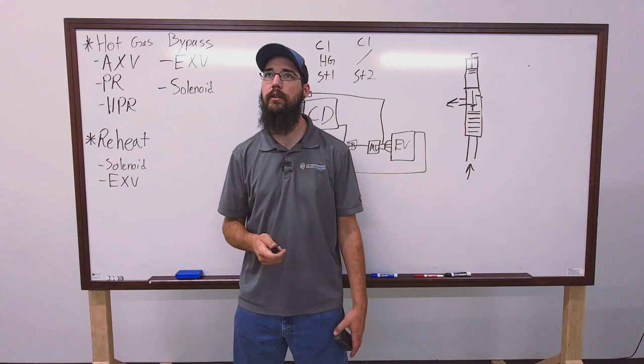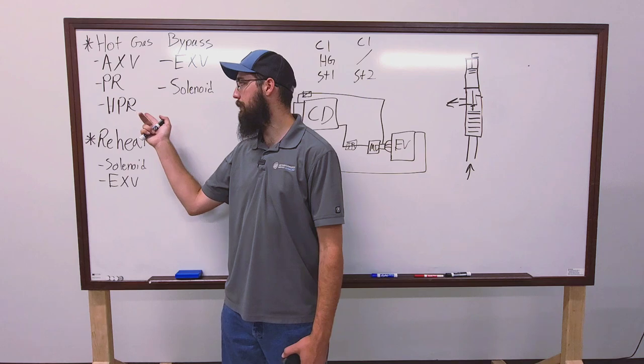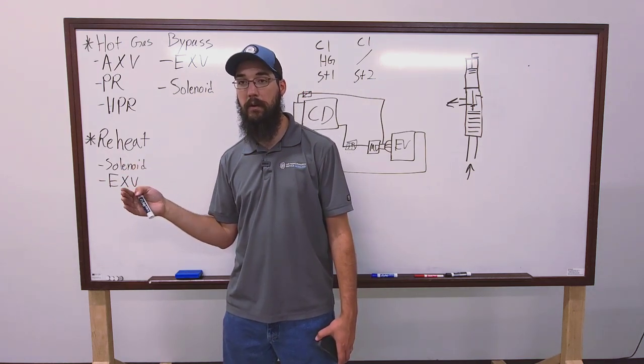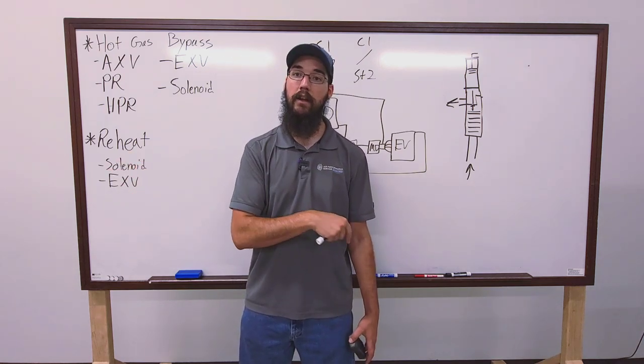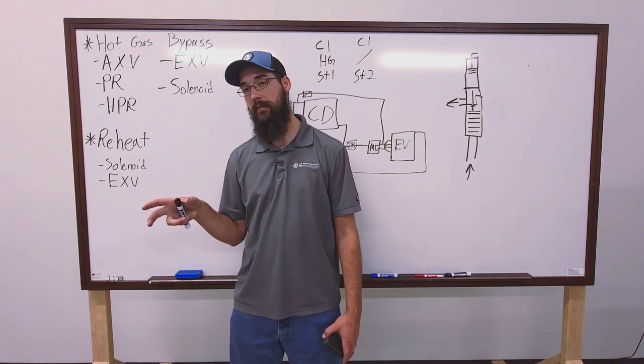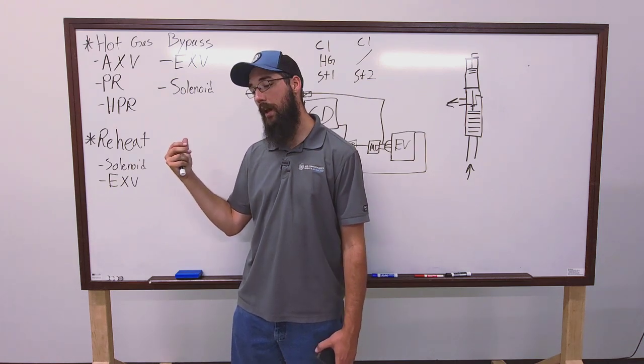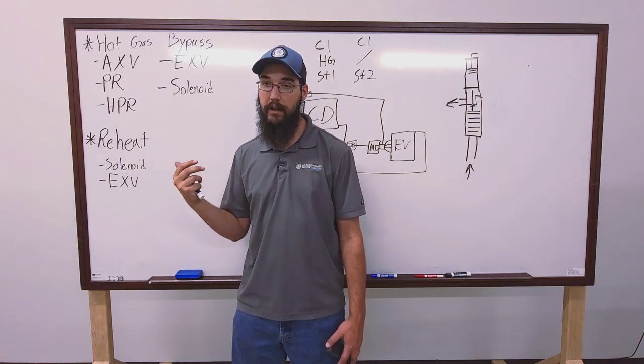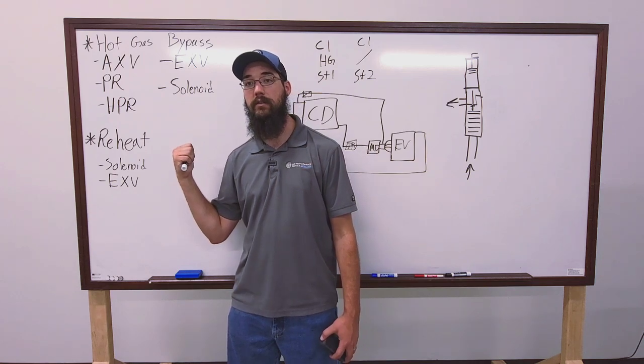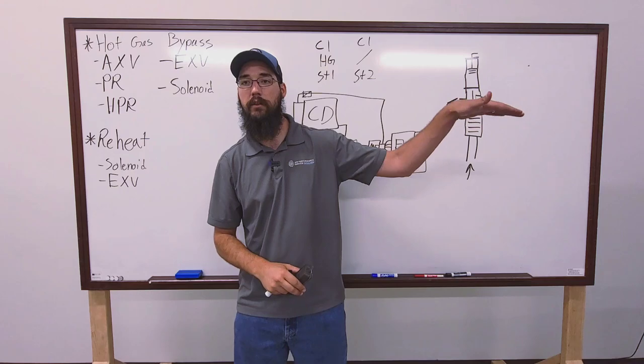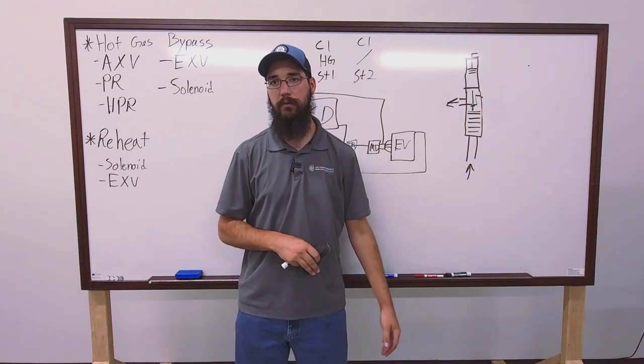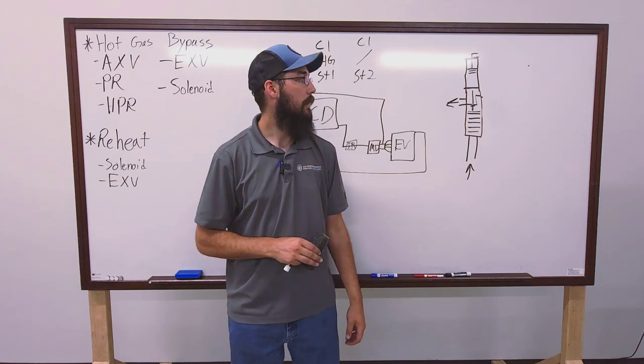They won't have that same style power head assembly. So, with the HPR, you wouldn't typically see that with an unloader as well because they're kind of accomplishing the same practice? I mean, ultimately, you could... The point of HPR is still to regulate under... Honestly, they're more of a low ambient load. So, they're bypassing to regulate for low outside temperatures, not necessarily inside. The rest of these, their focus is the inside saturation and HPR is focused on the outside saturation. So, head pressure control. Right. Exactly. So, with that, you wouldn't necessarily need fan cycling. Okay. So, if you had a head pressure regulator, you won't need fan cycle control. You just use that. The fans can run all the time as normal and that's just going to bypass enough hot gas from the condenser to where it's going to keep your liquid line elevated where you need it so that it still can properly still have your differentials.